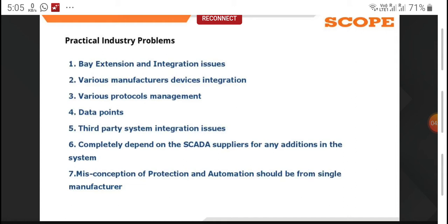Then there is protocol management. Relays are on 61850, but when it comes to the MFMs or meters, those are all on Modbus. Now, when you are configuring a system in the substation, if you choose single 61850, every piece of equipment should talk on 61850, so that the HMI and the network are on a common protocol.